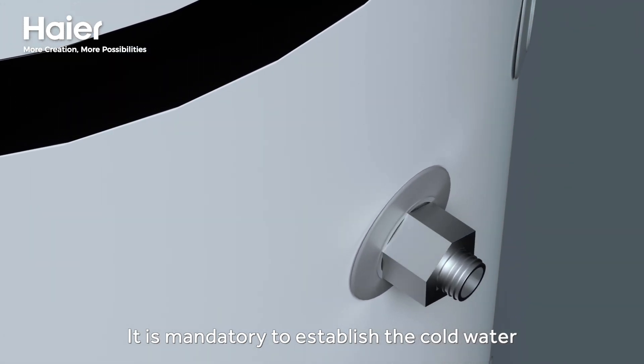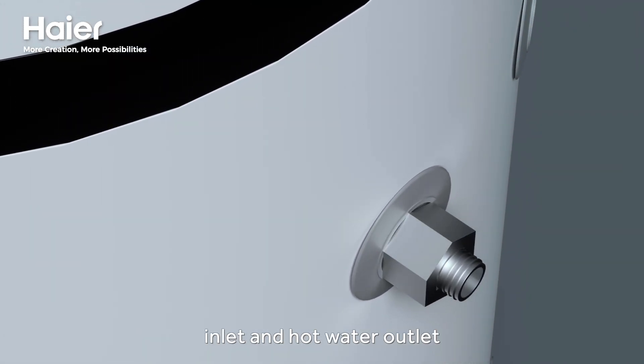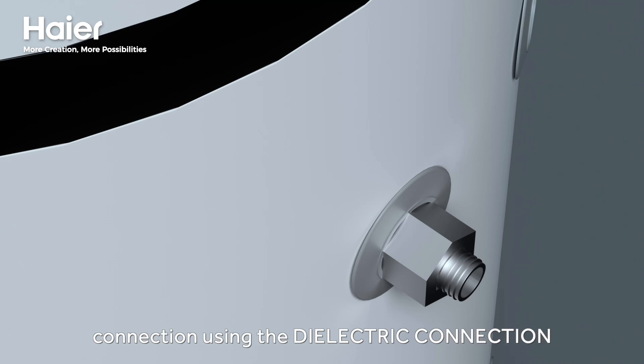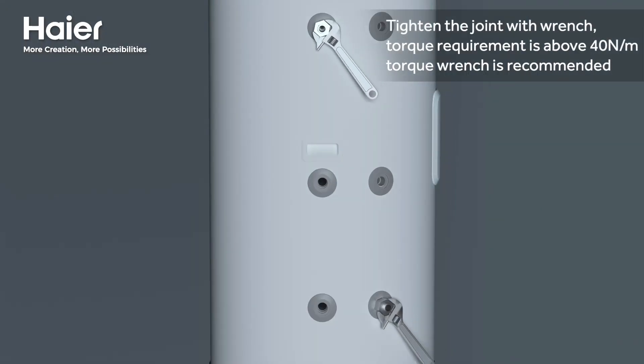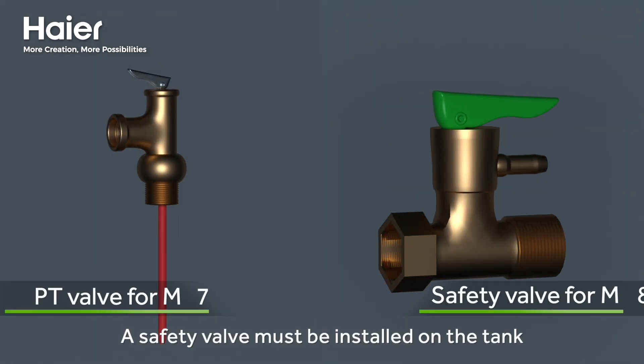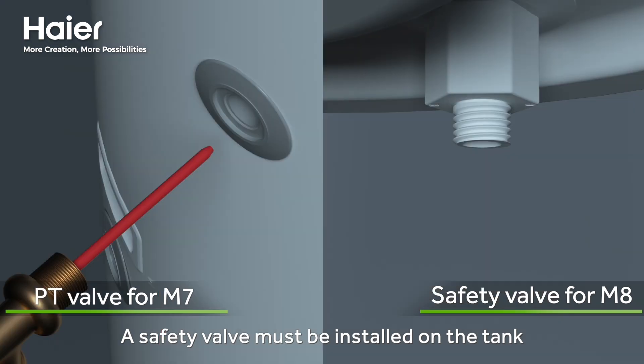Establish the cold water inlet and hot water outlet connection using the dielectric connection. Tighten the joint with a wrench. The torque requirement is above 40 Newton meters — a torque wrench is recommended. A safety valve of 8 bar must be installed on the tank.